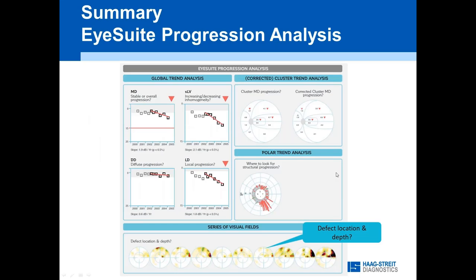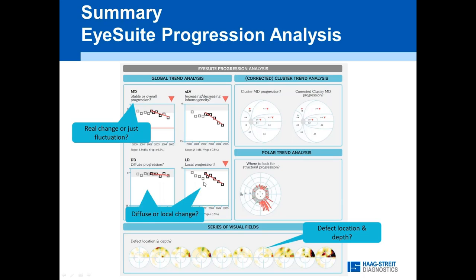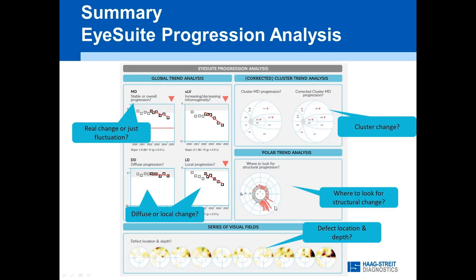To summarize: the series gives you the absolute location and depth of defects, important for clinical decision-making. The progression analysis tells you about change and probability of change. The MD answers whether there's overall change or just fluctuation. The DD and LD progression tell you whether change is diffuse or local. The cluster trend analysis shows which clusters are changing. And the polar trend analysis shows where to look for structural change.